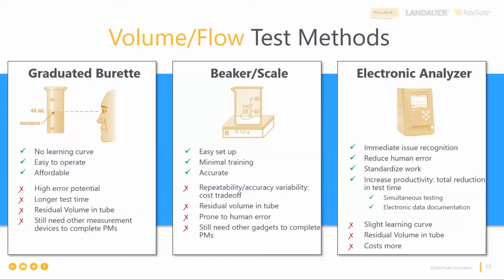Thank you, Jerry. And now let's move on to the electronic analyzer. So just like any other method, it has its pros and cons to it. The biggest benefits to using an electronic analyzer for testing infusion devices that we see is obviously the increased productivity and a huge reduction in test time, because first of all, you can do simultaneous testing if you're using a multi-channel analyzer. So you can connect multiple pumps to one analyzer and start your testing simultaneously.